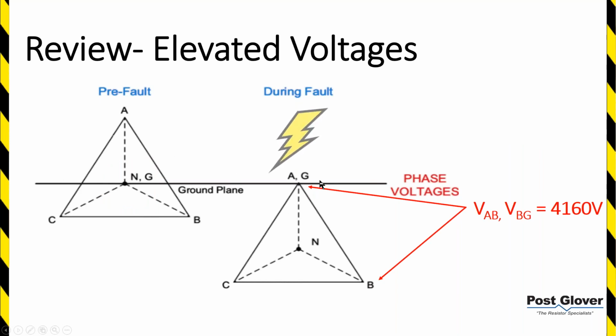Now this shifts away from the ground plane, shifts down, shifts up, whichever orientation you want to say. But essentially the phase-to-phase voltages stay the same, so that's good for your motors, etc. But the two non-faulted phase voltages are going to elevate from a line-to-neutral value to a line-to-line value. This is definitely a consideration when we're designing systems. If you're going to continue to operate with a fault, you're going to have these voltages in reference to ground, so it's important to make sure your equipment is protected for those voltages.